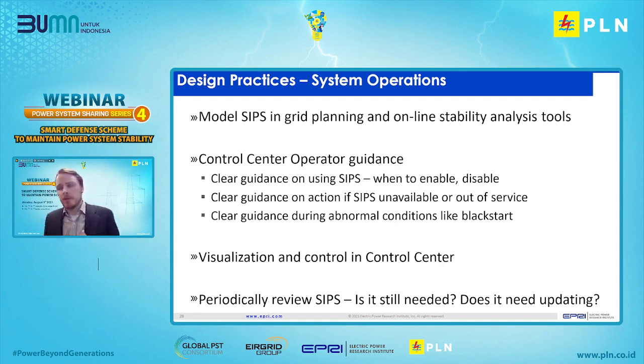We can see that these schemes can provide very effective means to identify abnormal system conditions, be it oscillations or overloading, and prevent them. But it's very important as part of the grid planning and operations phases to ensure that these schemes operate correctly and as expected. When they're being used in the control center, it's extremely important that there's clear guidance to the system operator on how to use the schemes, when to enable them, when to disable them, what to do if the protection scheme is out of service or a relay has failed, and how to use them in abnormal conditions like during black start or system restoration. Also visualizing and control within the control center to ensure that it presents meaningful information. A very good example was shown in the previous presentation, where it showed the status of the SPS and the operator can see exactly how it is operating.